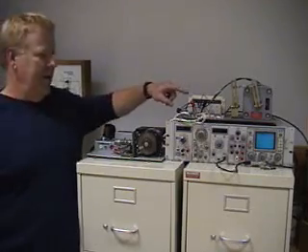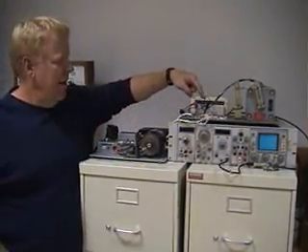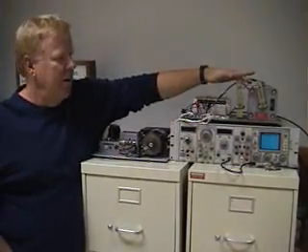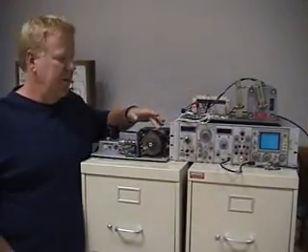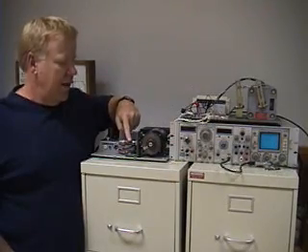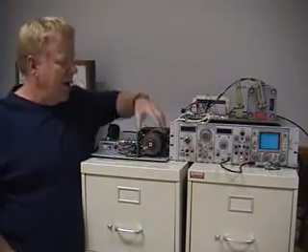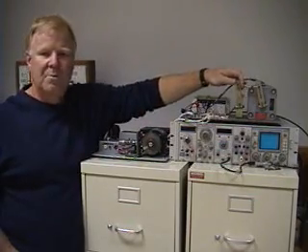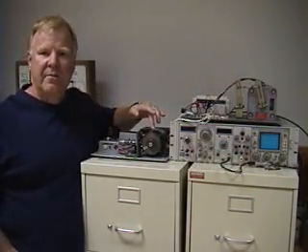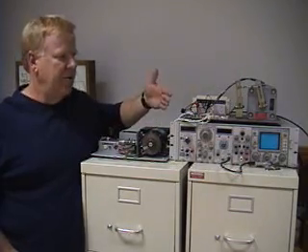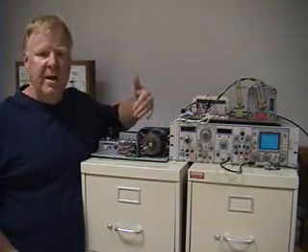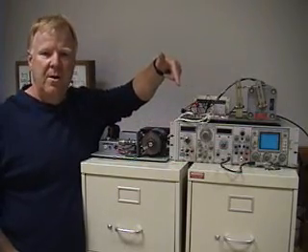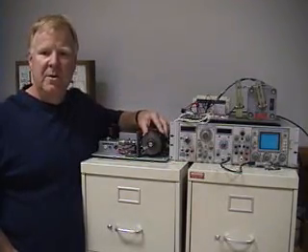What we have here is a closed loop speed simulator with a speed control driving an all-electric actuator. The speed control is getting its speed signal from a magnetic pickup. The controller here is driving a DC motor, so as the speed control requires more fuel, it's going to send a higher DC voltage to drive it faster. As it needs less fuel, it's going to give it less DC voltage and slow it down. So we have a complete closed loop system here running speed control.